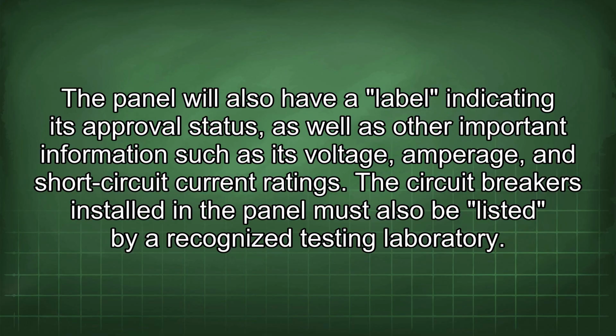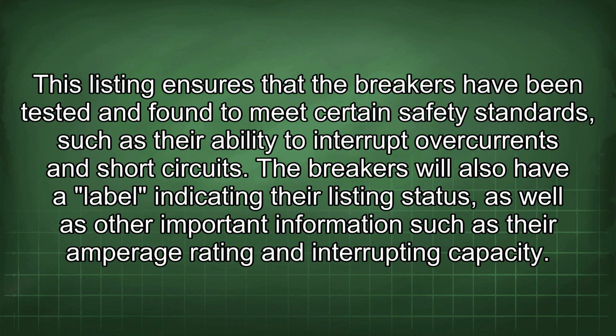The circuit breakers installed in the panel must also be listed by a recognized testing laboratory. This listing ensures that the breakers have been tested and found to meet certain safety standards, such as their ability to interrupt overcurrents and short circuits. The breakers will also have a label indicating their listing status, as well as other important information such as their amperage rating and interrupting capacity.